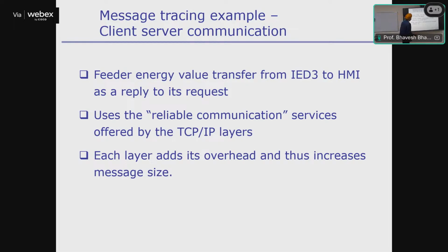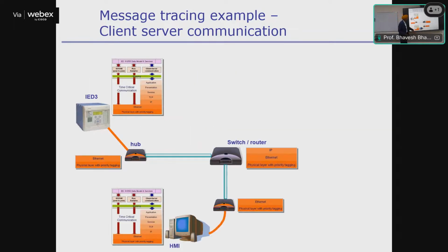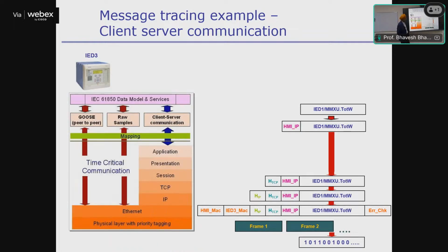Now for client-server communication, let's say we want some energy values transferred from IED3 to the HMI. This is a reliable service now - it's going to use all the layers, but each layer will add its own overhead, increasing the message size. So IED3 to HMI: let's say we are sending the total watts value, where MMXU is the logical node for measurements. Then it goes to the HMI IP, and TCP will add its own overhead, the IP layer will add its own overhead, and eventually the message will become very long.